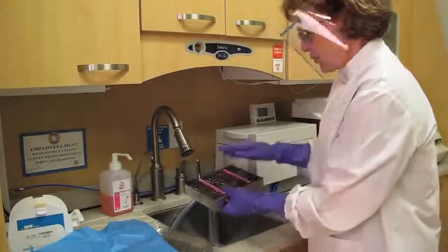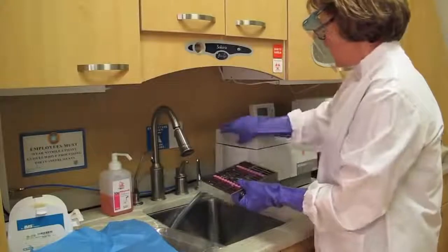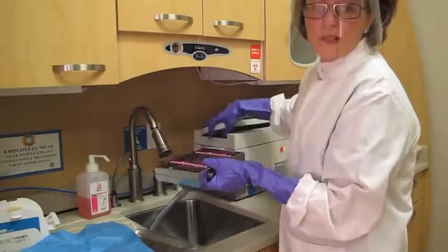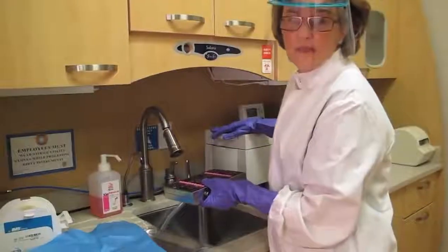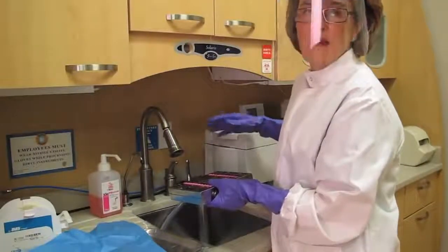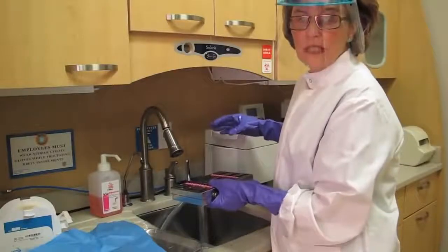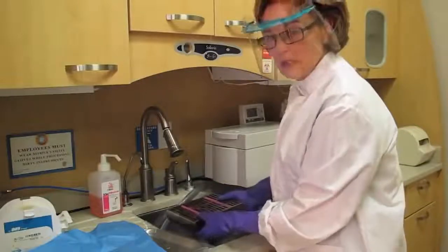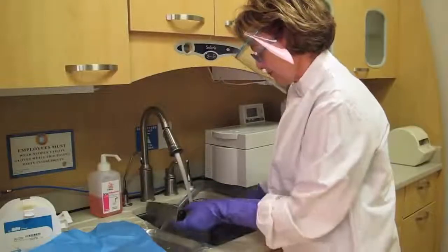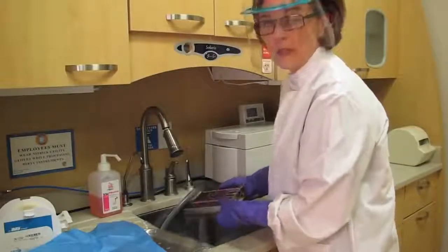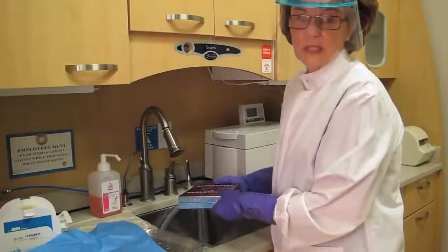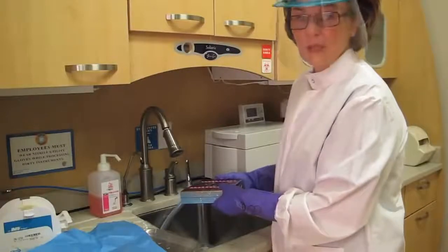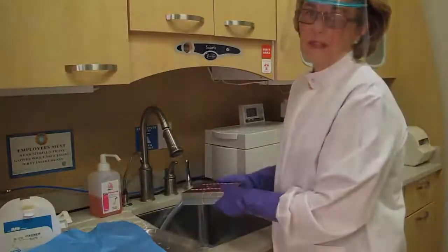The next step, once it's rinsed, is to put the instruments in the ultrasonic. You also can put them in a washer disinfector. Either way, the next step is mechanical cleaning. And after that, you rinse it again if it's been in an ultrasonic, and then open it, and then inspect your instruments, and only then, if you need to scrub them or further clean them manually, that's when you do that.